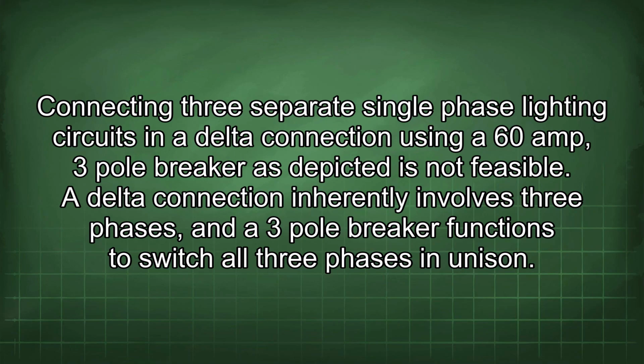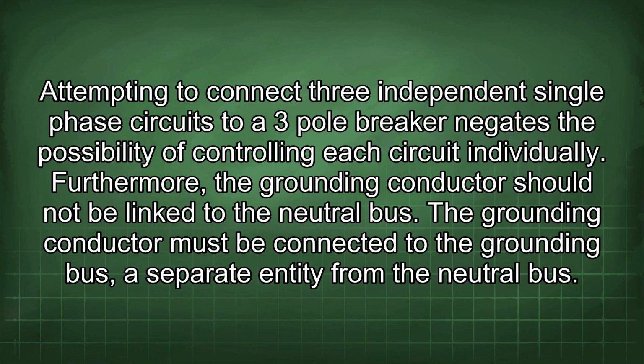Connecting three separate single-phase lighting circuits in a delta connection using a 60-amp 3-pole breaker as depicted is not feasible. A delta connection inherently involves three phases, and a 3-pole breaker functions to switch all three phases in unison. Attempting to connect three independent single-phase circuits to a 3-pole breaker negates the possibility of controlling each circuit individually. Furthermore, the grounding conductor should not be linked to the neutral bus. The grounding conductor must be connected to the grounding bus, a separate entity from the neutral bus.